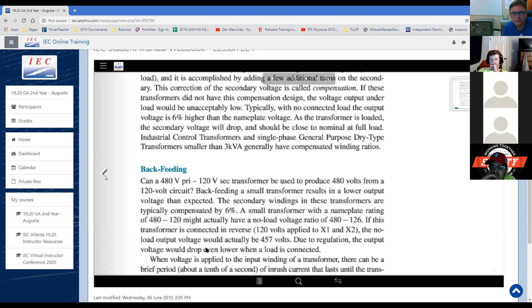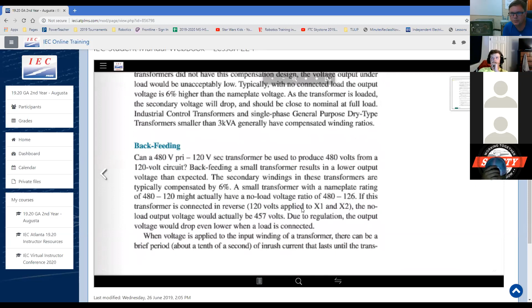So in these instances, backfeeding them would be bad because you would be going 120 to 7200 volts. But in a smaller dose, if you needed something on the job to be 480 and you only had 120 coming in, could you backfeed? And that's what they're talking about here. With the transformer connected in reverse, the no load output voltage would actually be about 457. It'd be a little lower. Due to regulation, the output voltage would drop even lower when the load is connected. So you're not going to get that full amount.